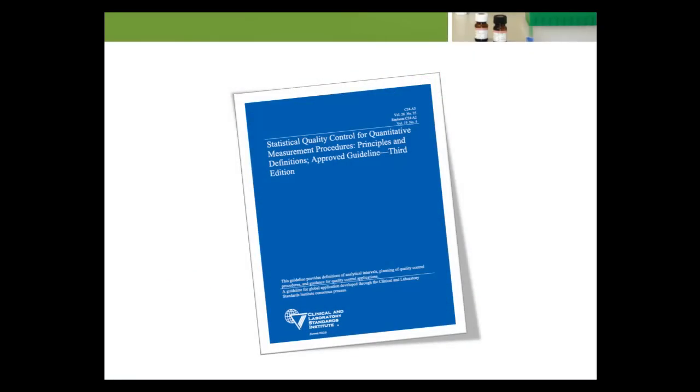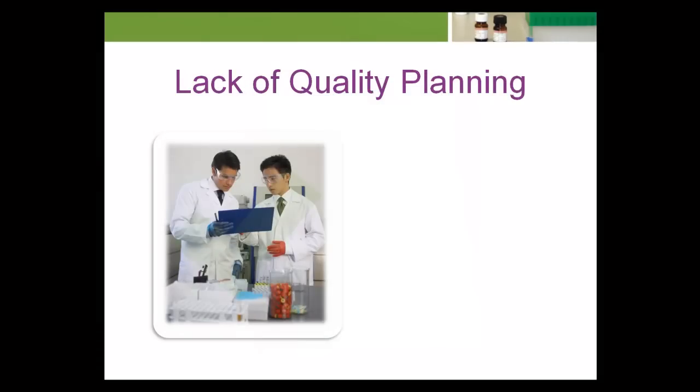As stated in this CLSI standard, the first step to planning an effective quality control procedure is to define the intended quality for a test. While laboratories will devote time ensuring a new instrument, kit, or method meets manufacturer claims, many do not plan for how much imprecision and bias is acceptable for a test. Consequently, such laboratories often set process control rules that intuitively may seem appropriate or reflect past experience, but inherently discount the technical aspects of the test that directly relate to analytical quality.